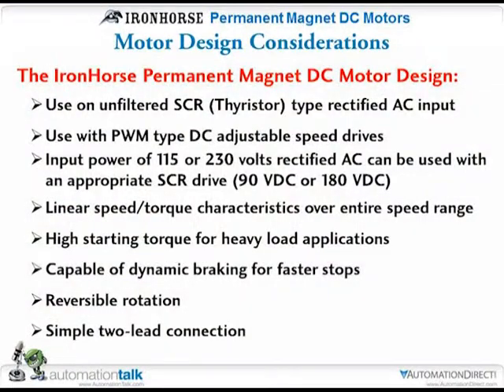These motors were designed so they can be used with SCR type controllers as well as PWM. DC motors over the years have either been designed to operate from 90 volts DC or 180 volts — that comes from the fact that we can take 115 VAC and rectify it to get 90 volts DC, or use a 230 volt single phase source to get 180 volts DC. These motors offer linear speed and torque characteristics, high starting torque on heavy loads, dynamic braking capability, and simple two-lead construction.